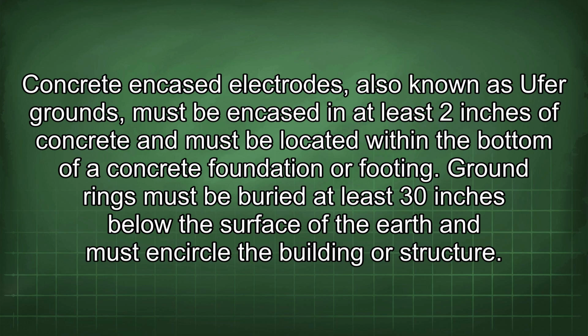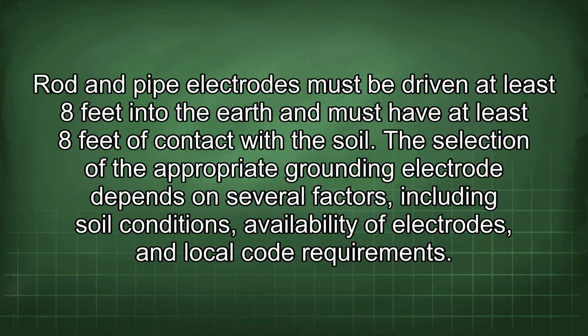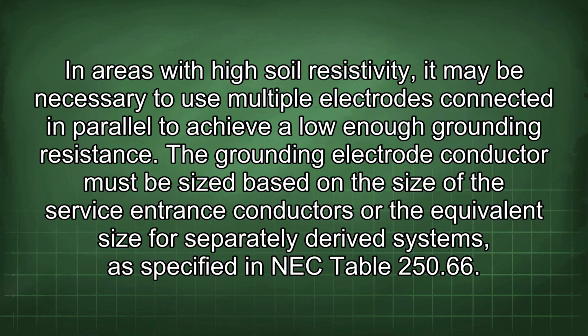Ground rings must be buried at least 30 inches below the surface of the earth and must encircle the building or structure. Rod and pipe electrodes must be driven at least 8 feet into the earth and must have at least 8 feet of contact with the soil. The selection of the appropriate grounding electrode depends on several factors, including soil conditions, availability of electrodes, and local code requirements. In areas with high soil resistivity, it may be necessary to use multiple electrodes connected in parallel to achieve a low enough grounding resistance.